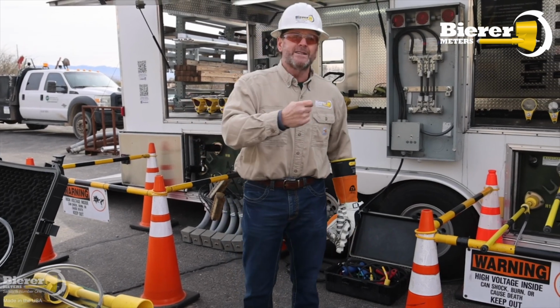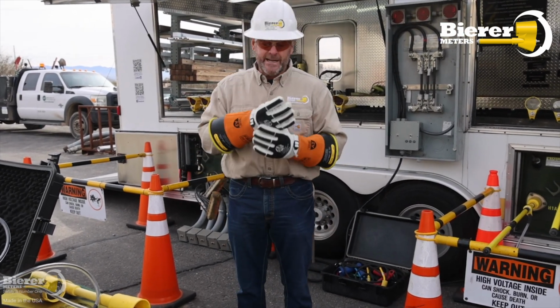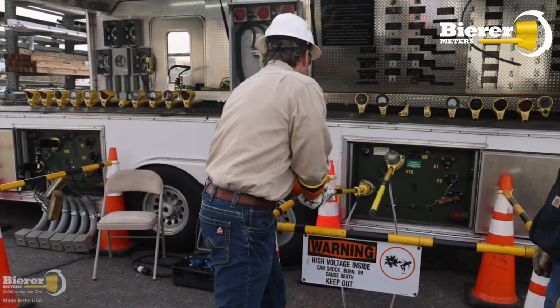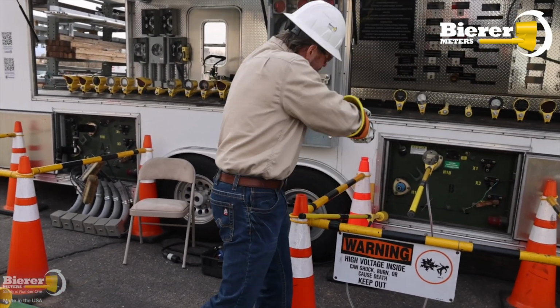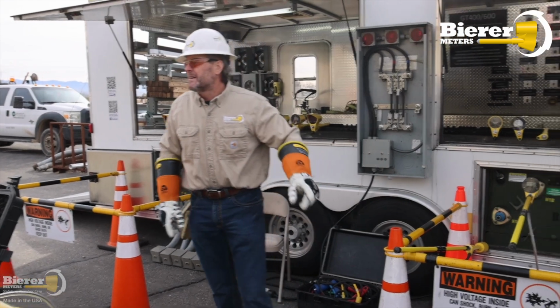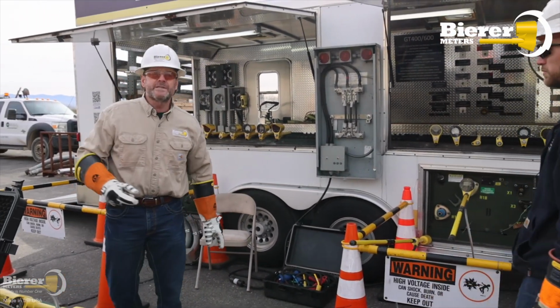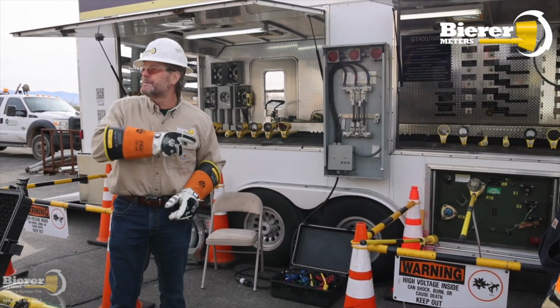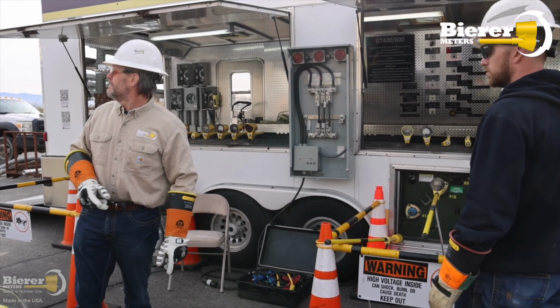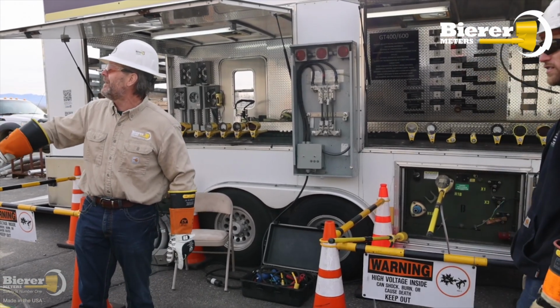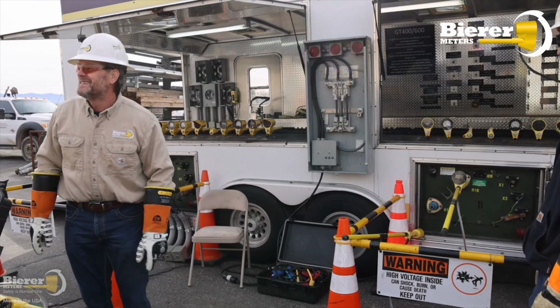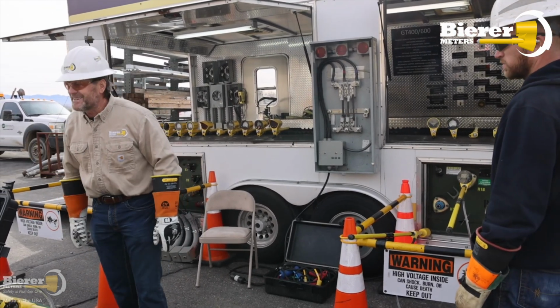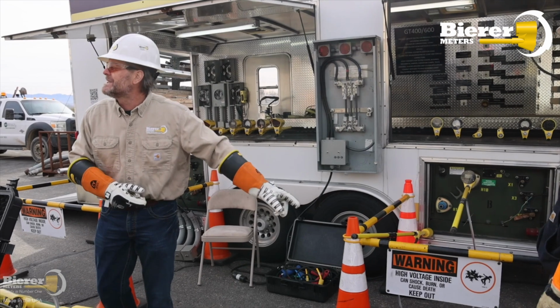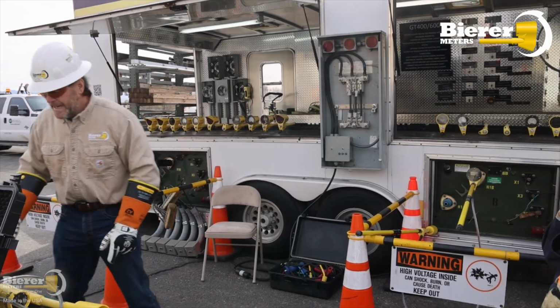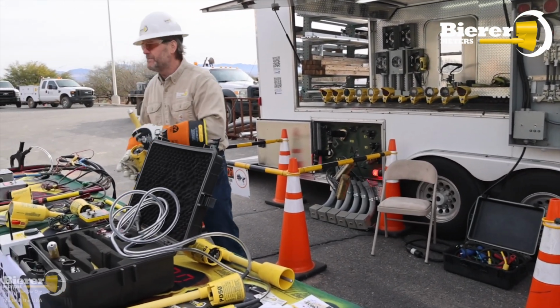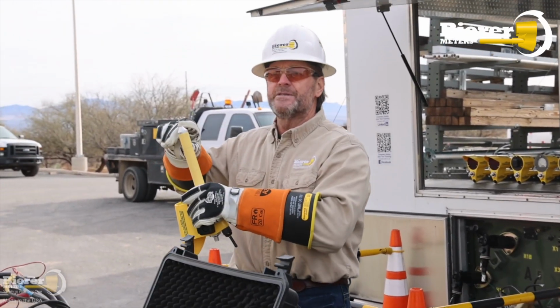And you're going to use the tool to give you the information that the tool is de-energized. So the way to do that is we're going to go to the ground first with the secondary probe, and then when CJ pulls the tool off that overhead line, he'll notice that it takes about 2 seconds to bleed off that capacitance, all right, on that conductor or the capacitance within the tool. It takes about 2 seconds.